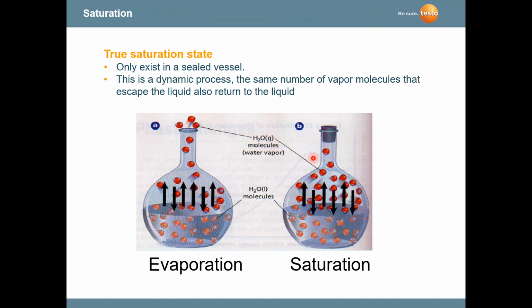Now, we get back into the pressure side of things and getting inside the air conditioning system itself. As I indicated on the previous slide, as we add heat to the refrigerant, we're changing it from a liquid to a vapor. And as we remove heat, we're going from a vapor to a liquid, or it's condensing. If you look at this illustration, we are dealing with saturation in sealed vessels, which is an air conditioning refrigeration system.